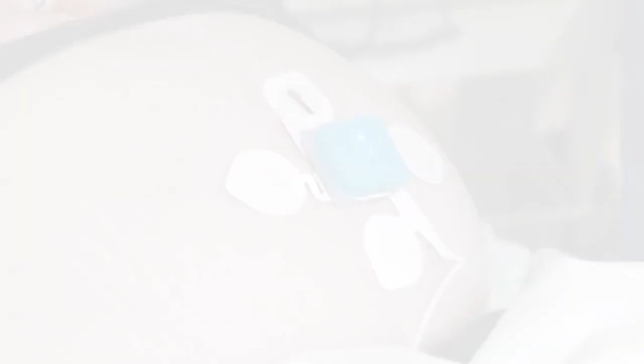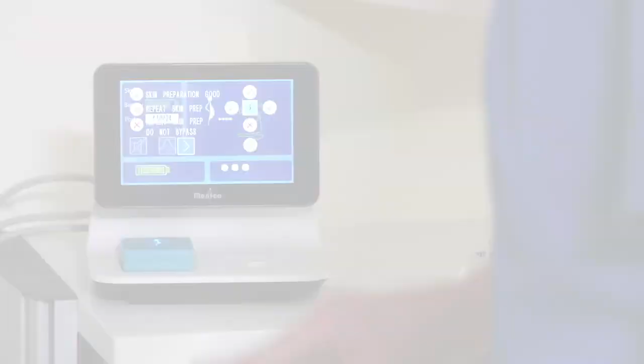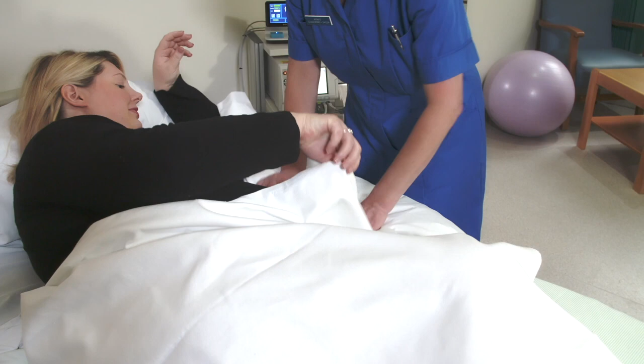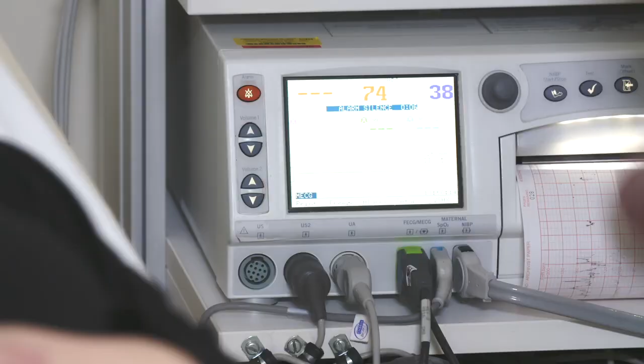An electrode has come detached. This will be flagged up by the Novii system and should be corrected. Another cause is bypassing a red cross during setup, or incorrect electrode placement, especially when the symphysis pubis is difficult to locate. In large moms, you may need to support the abdomen with a pillow or rolled blanket if they are lying on their side and the patch has been shifted away from the center of the uterus. One of the main advantages of the Novii system is that you can plug an ultrasound transducer into US 2 or 1 port of the Coro 259CX and fill short gaps, especially those that can occur towards the end of stage 2 when the mom is pushing. Novii is vulnerable to gaps during pushing in stage 2.